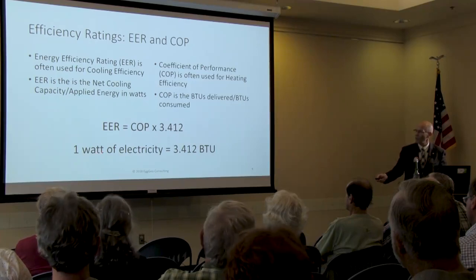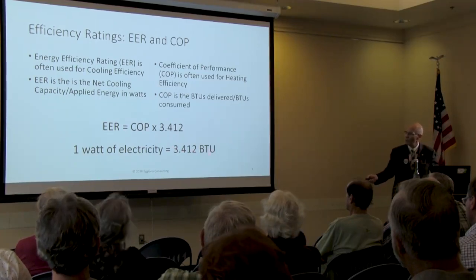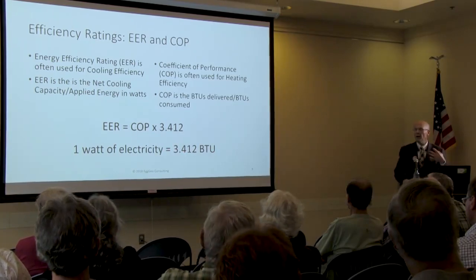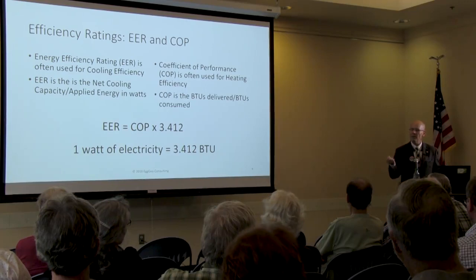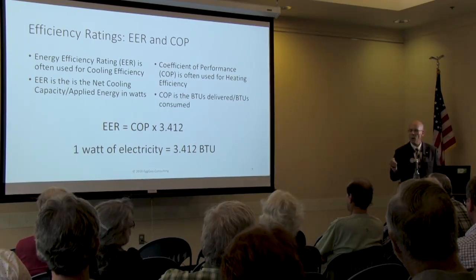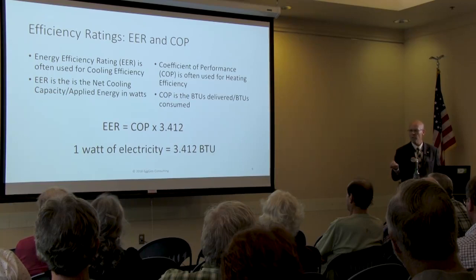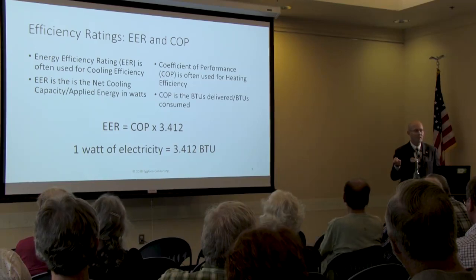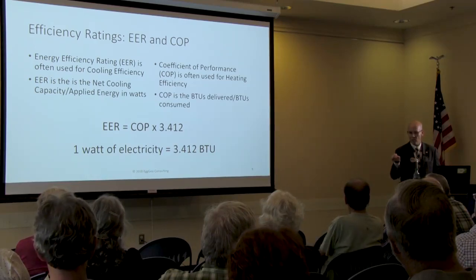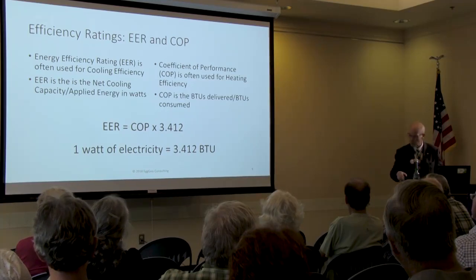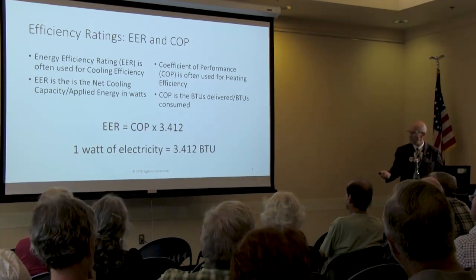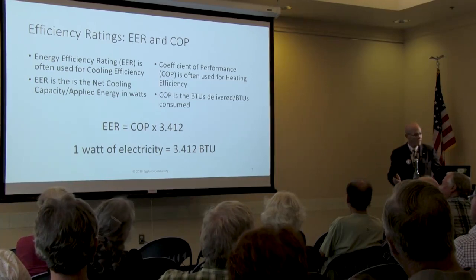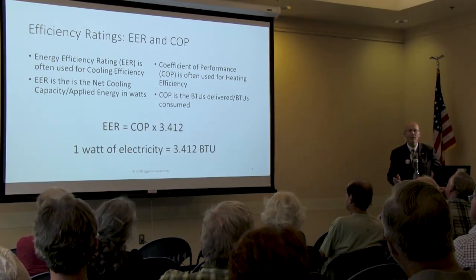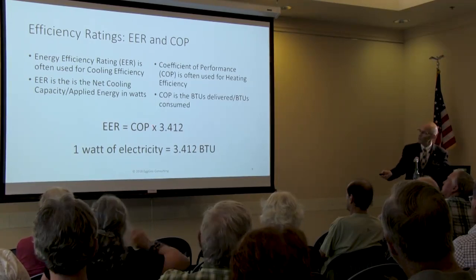A couple of quick correlations. 1 watt of electricity equals 3.412 BTUs. A BTU, just to get down to basics, is the same amount of energy it takes to raise 1 pound of water 1 degree Fahrenheit. It's also, just to give you a burn characteristic, the equivalent heat that's given off by burning one wooden match from top to bottom. That's about one BTU. So 1 watt of electricity is equal to about 3.4 matchsticks burned, or about 3.4 degrees of temperature increase in 1 pound of water. So there is a correlation here.